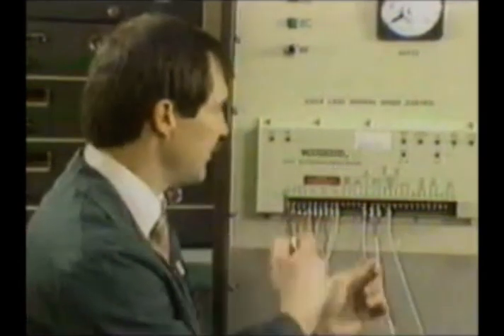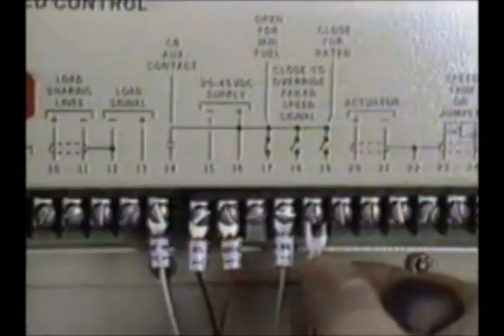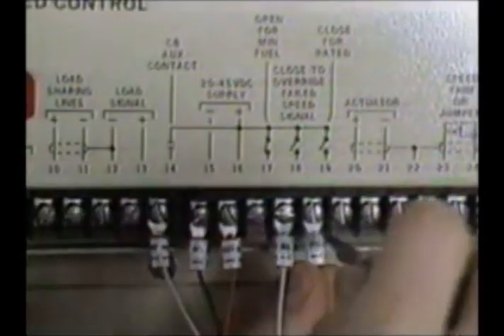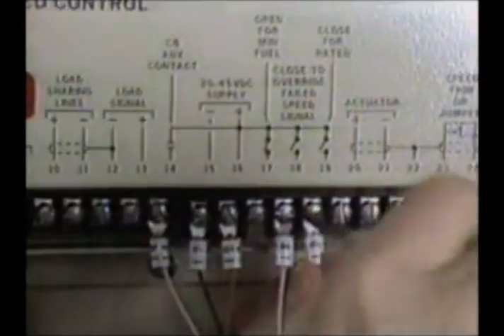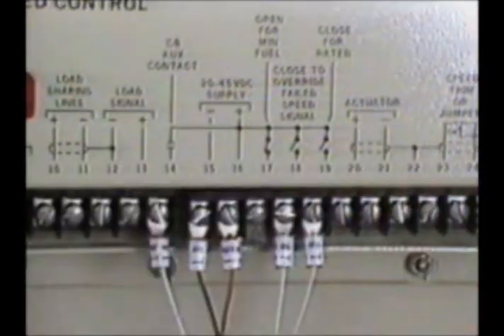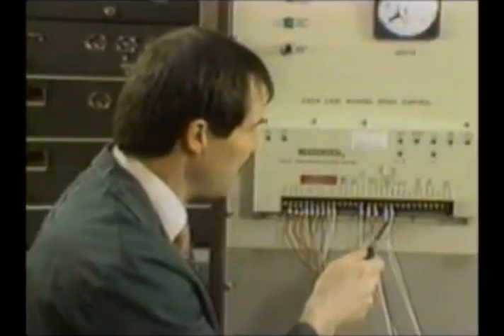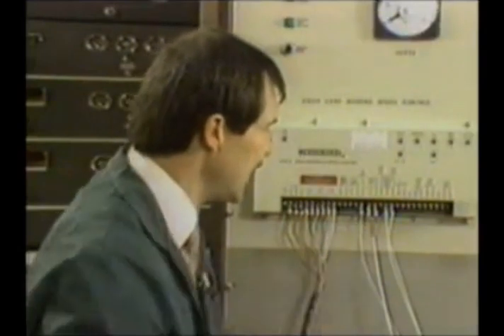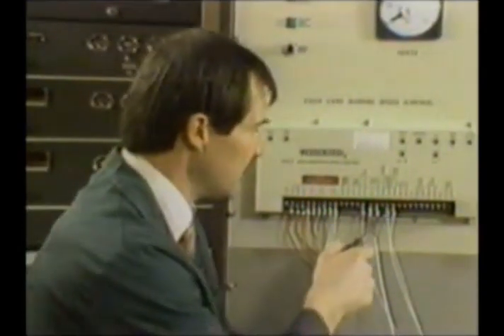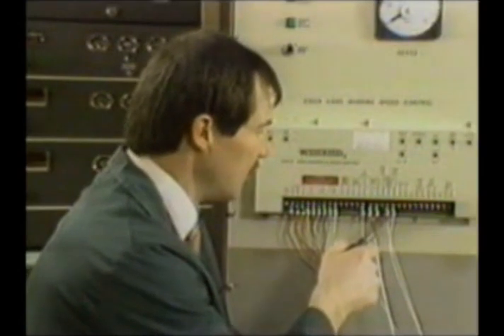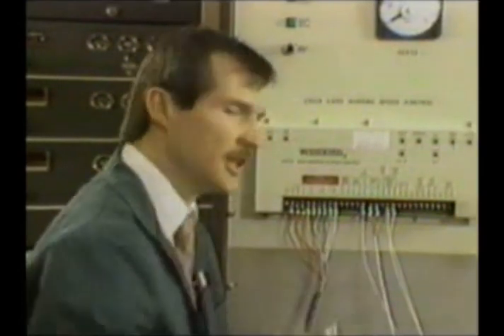Terminal 19 is closed for rated. This will let you go from idle speed up to rated speed. I have a switch for that. What I do on all these terminals, 14, 17, 18, and 19, they need to be provided with the positive side of the input voltage to control them. So as soon as I put a voltage on terminal 19, we'll ramp up to rated speed.